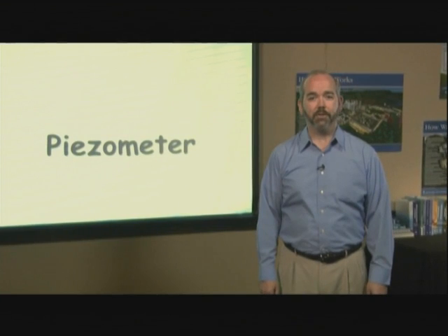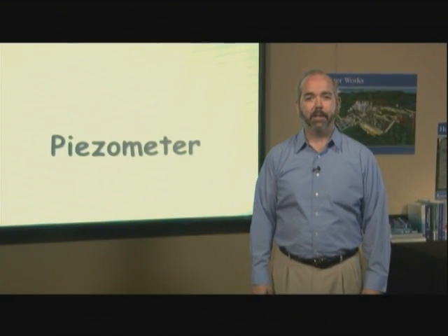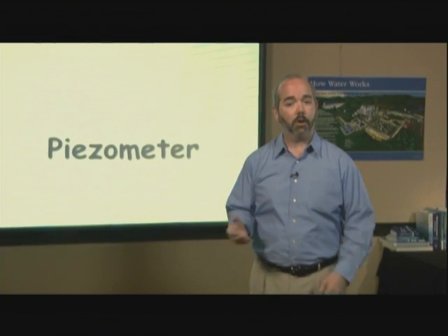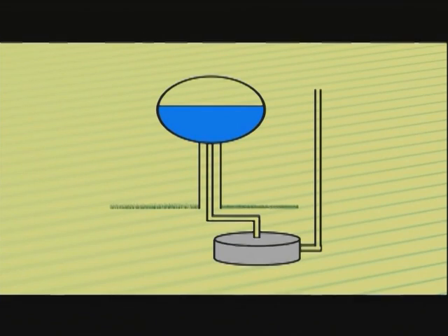Another instrument that is used to measure water pressure head is a piezometer. Think of it as a water level used on a larger scale. What happens if we have an elevated tank connected to a tank that is down on the ground? Assuming the ground tank has a top to keep water contained, the water is going to come out of the elevated tank and go into the lower tank under pressure, and we can determine that the pressure will rise to approximately the same level that is in the elevated tank minus any friction loss.